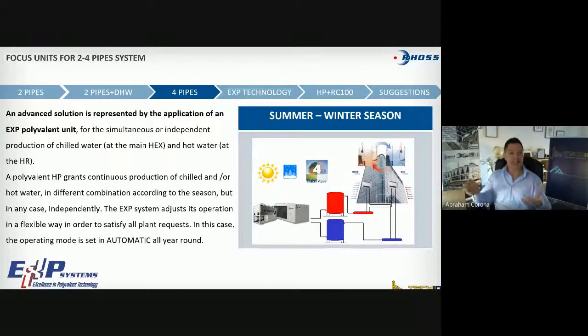Moving forward, what is an EXP technology? It's exactly that. It's basically a smart heat pump that is able to comply with any possible situation coming from a 4-pipe system. If you need only cooling, if you need only heating, and if you need simultaneous heating and cooling. Keep that in mind. The next slides are going to become a little bit more technical, but a little bit more interesting, because I will explain how one unit, an EXP RHOSS unit, can satisfy that in an automatic way, automatically by the controller. In other words, the only set point you need to set in one of the EXP units from us is the outlet temperature you want out of the unit in heating, let's say 55, and the outlet temperature you want out of the unit in cooling, let's say 7.